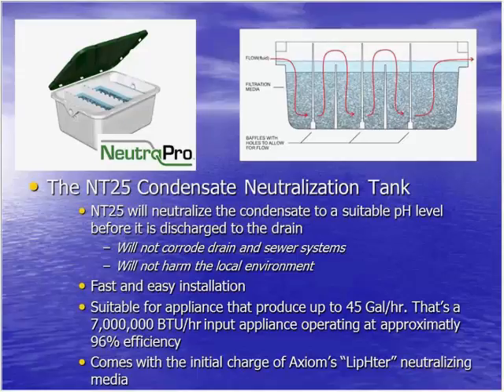There's also a built-in bypass overflow. So should this become neglected, with the media not changed or the unit not cleaned out as part of the normal service, it's not going to back up into the boiler. There's a built-in bypass overflow channel to allow that to bypass if required. And this is suitable for appliances that produce up to 45 gallons per hour, which is about a 7 million BTU per hour input appliance operating at 96%. And of course, it comes with the initial charge of media.